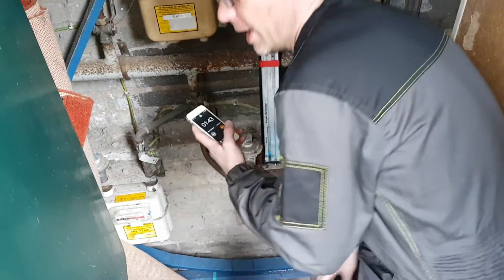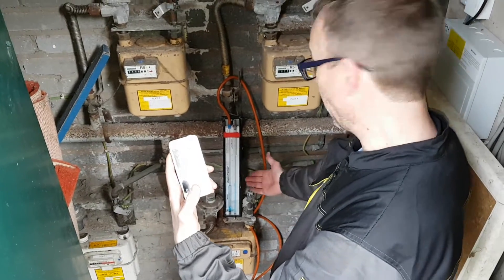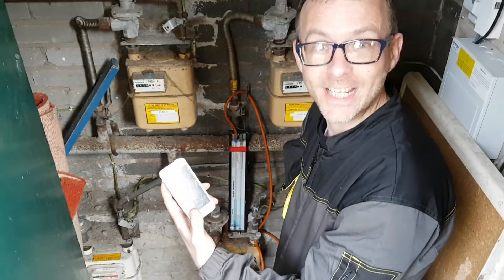So now doing my two-minute tightness test — we're counting down at the moment here. I'm just going to note any drop or rise in the manometer gauge.